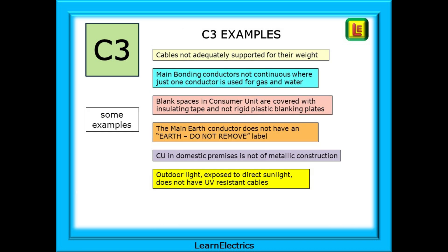Here are a few more C3 examples. You will come across installs where the main bonding conductors are not continuous — where the pipes are next to each other and just one earthing conductor is used for the gas and water, terminating at the gas pipe with a second conductor linking to the water pipe. The problem is that the gas bonding could be removed, leaving the water pipe without any main bonding. Another common one: outdoor lights connected with basic twin and earth cable with no UV stabilisation — after a few hot summers the outer sheathing will start to go hard and may crack or split. Think of C3s as being like advisories on an MOT for a car.